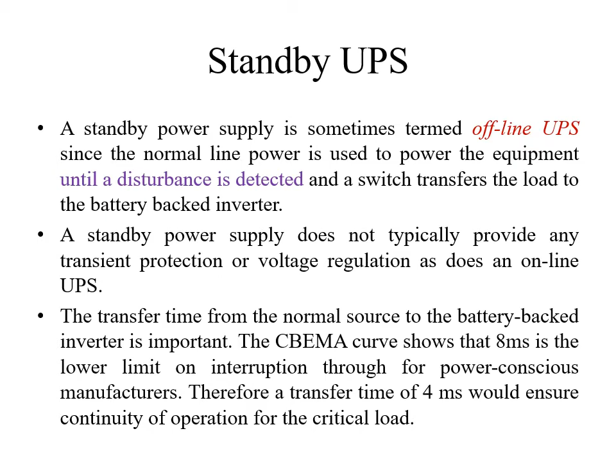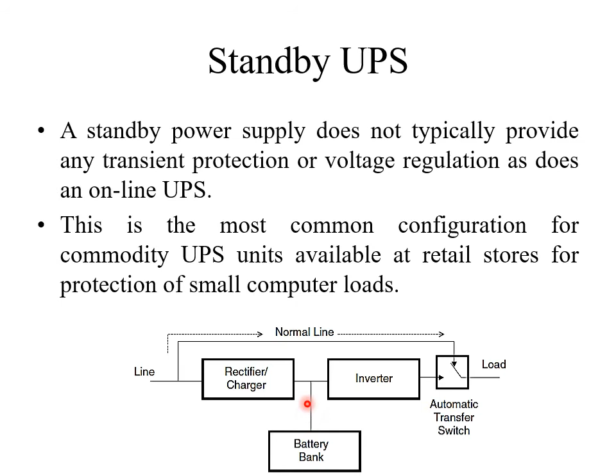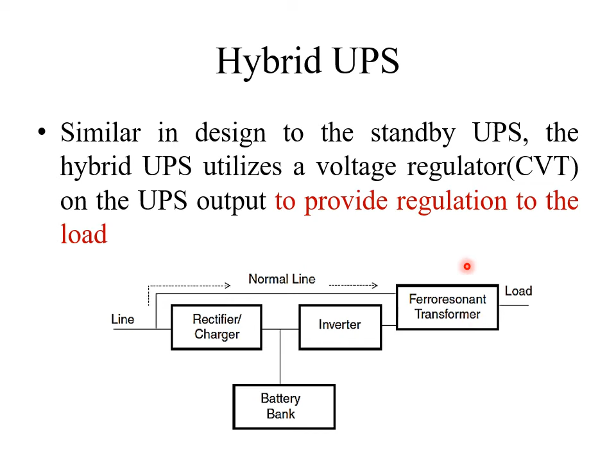Here you can see the automatic transfer switch and its application. Under normal conditions, the power supply passes through this, and when there is any disturbance in the normal power supply, this UPS system comes into operation. Hybrid UPS is the combination of the online and offline, adding a voltage regulator. You can see here this is the UPS system and a regulator, that is a CVT, constant voltage transformer, or ferroresonant transformer, used at the load side, and that makes the system hybrid.